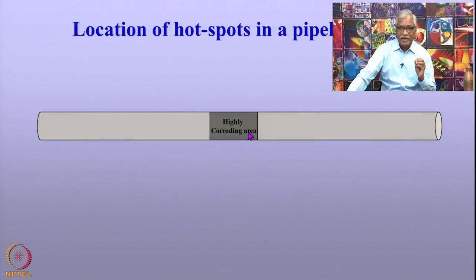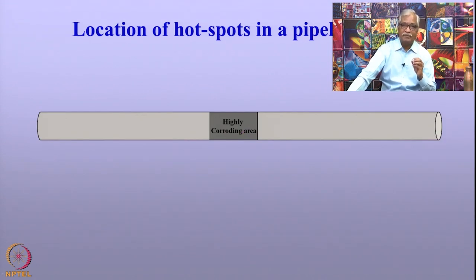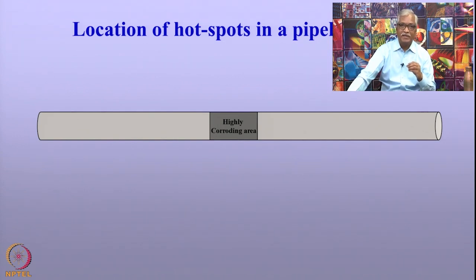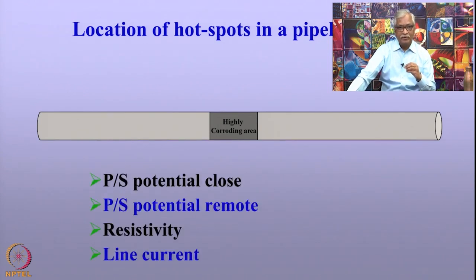The highly corroding areas are rendered as the anodes, and the other areas are rendered as cathodes. The current flows between the anode and the cathode — it leaves the anode, goes to the cathode, and flows through the pipeline. These are bare pipelines that are not cathodically protected. We can use three techniques — pipe-to-soil potential, resistivity, and line current measurements — to locate the segment of the pipeline experiencing severe corrosion.